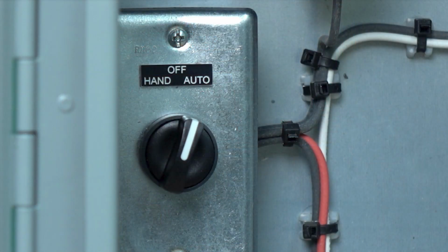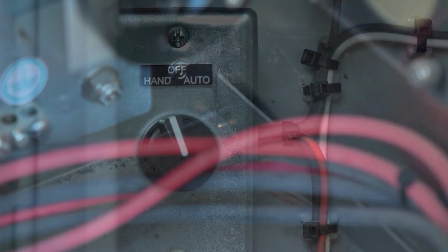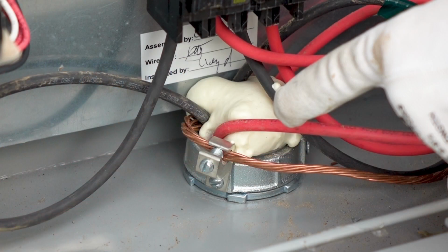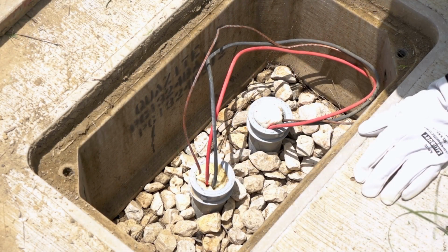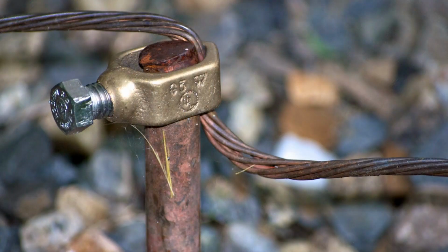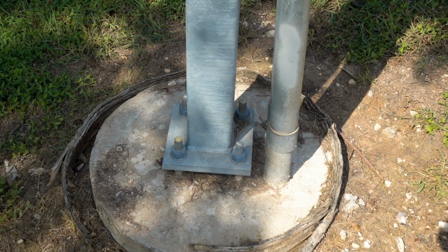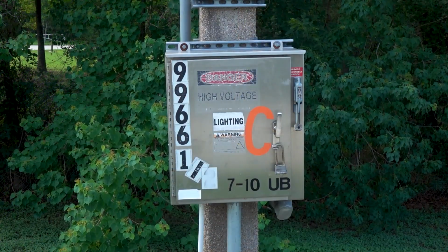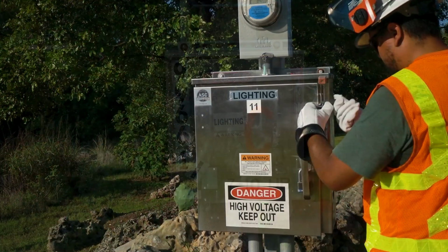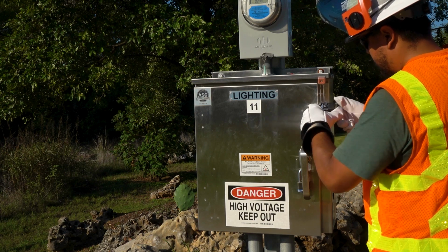Hand-off-auto switch works properly in all settings. Enclosure drain holes are provided. Conduit grounding bushings are installed. Underground conduits are sealed. A ground rod of correct size and length is properly installed for timber pole and granite concrete supports. For steel pole service supports, ensure the concrete encased grounding electrode was properly connected from rebar cage to the foundation anchor bolts. Service support structure is as specified. Work is done in a neat and workmanlike manner.